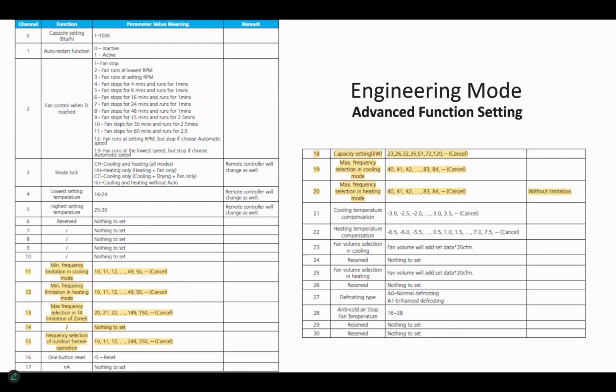All right, guys, in these ones here, let's talk about 16 first. 16 is a 1 button reset. So if somebody has gone in there and jacked around with the parameters and you have no idea what the parameters were before they changed them, you're screwed, because there's no list of what they actually are coming out of the box. You can use the one button reset, that resets it back to the factory defaults.